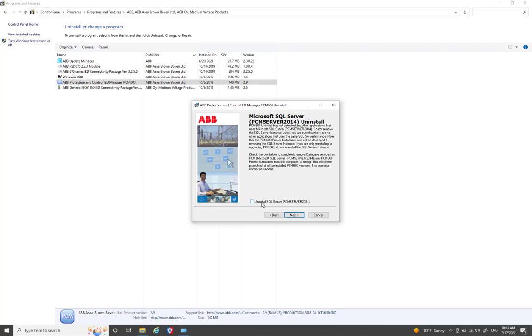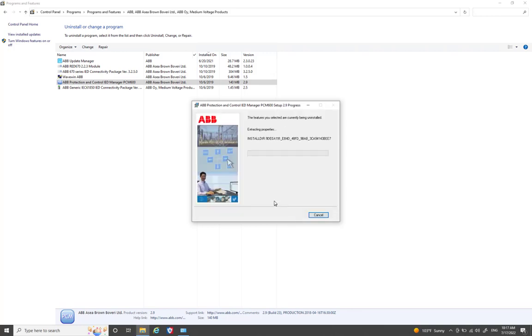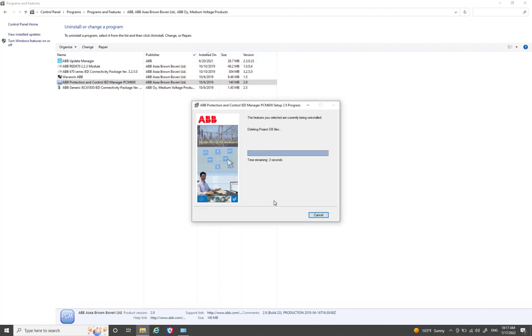You can also see the SQL Server instance that is required for PCM 600 to store project backups on the C drive. Before uninstalling, you need to export the different projects from the PCM 600 plant structure. Once you've taken proper backups, click Next to proceed. Depending on your PC's performance, the uninstallation will take a few minutes.